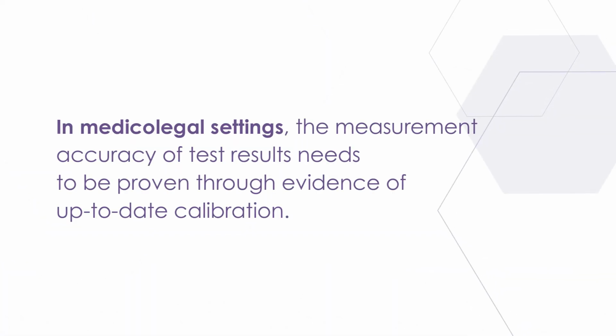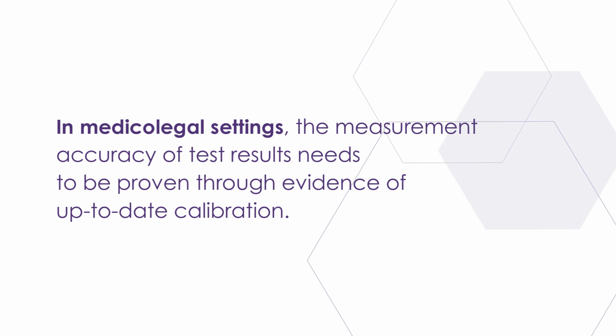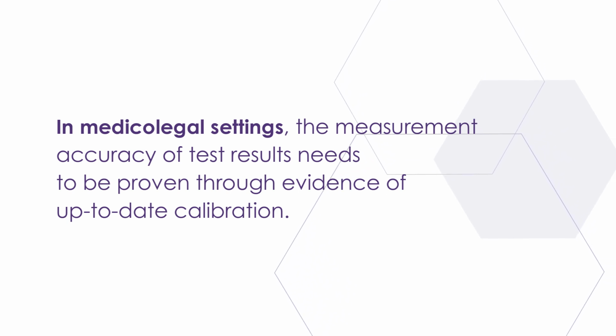Well, calibration is very important because the audiometric test records that we create from the tests themselves are actually a legal document in terms of they can be used in a medical legal case. Failure to update the actual calibration routine within a PC-based audiometer and instead just purely opting for a verification has the unintended consequence that the calibration date held within the audiometer software will be wrong.